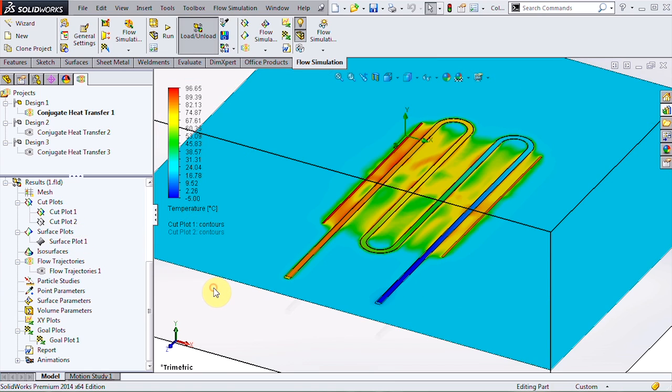We can take a look at a cut plot and see how the coolant changes temperature throughout the tube, starting at negative five degrees and reaching about 80 by the outlet.